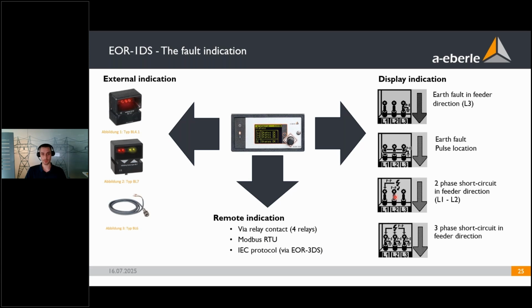Here you see a short circuit indication on phase 1 and 2, and this one is a short circuit indication in feeder direction as well on all of the three phases. But it's also possible to use remote indication. That could be done via a relay contact. The EOR-1DS has 4 relays, but it's also possible to use Modbus RTU and then connect it to your SCADA converter to use another protocol to reach your control center.